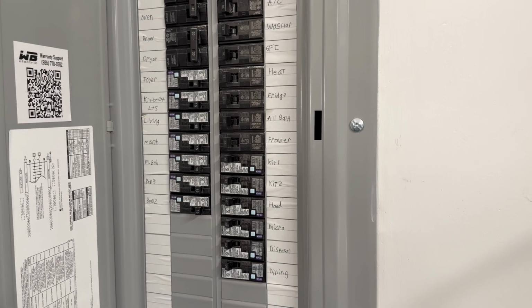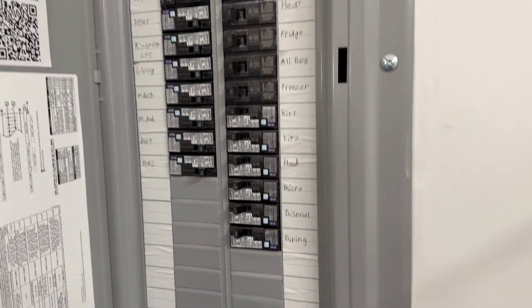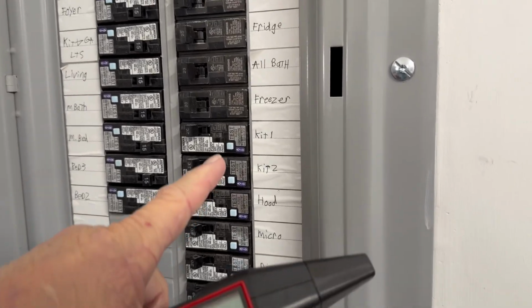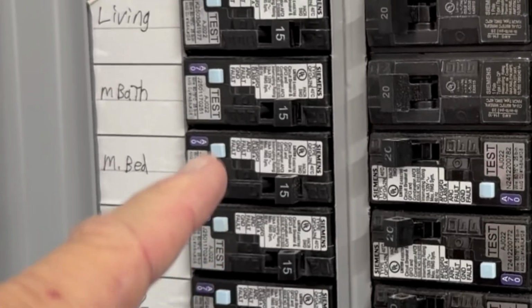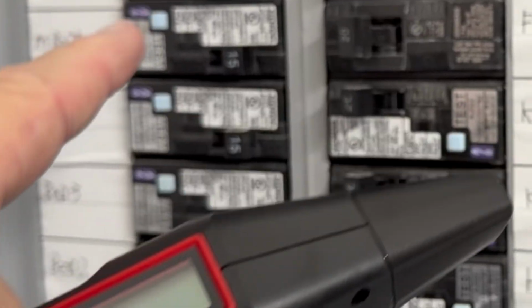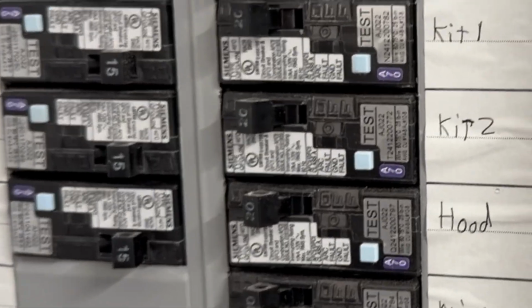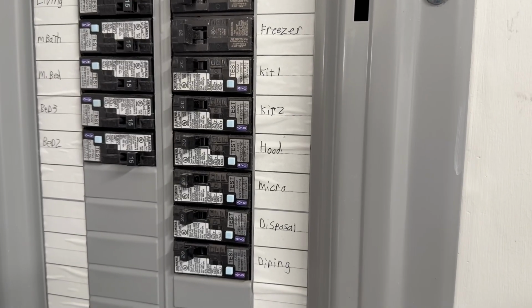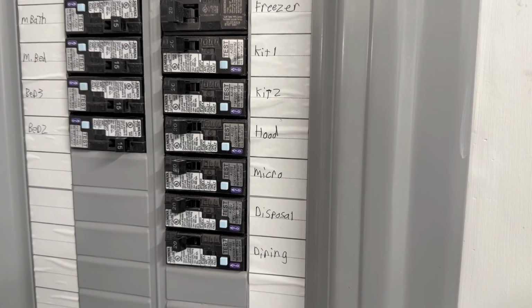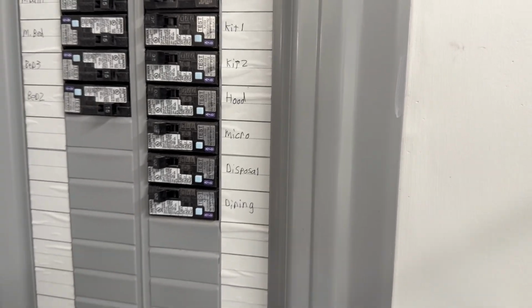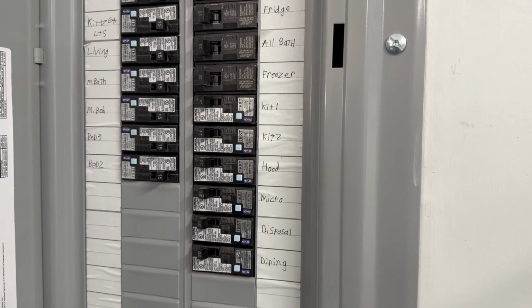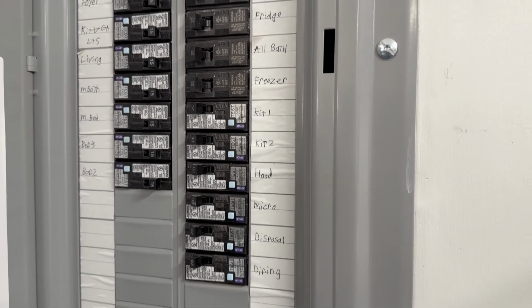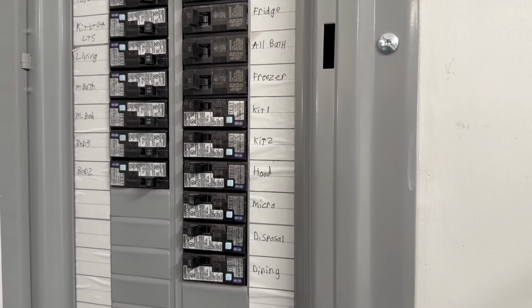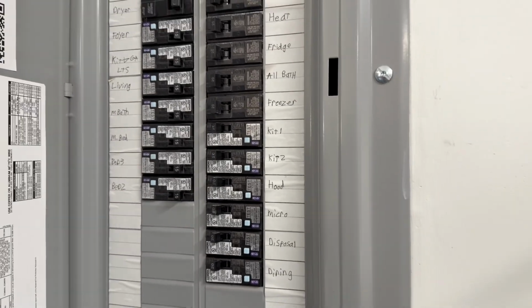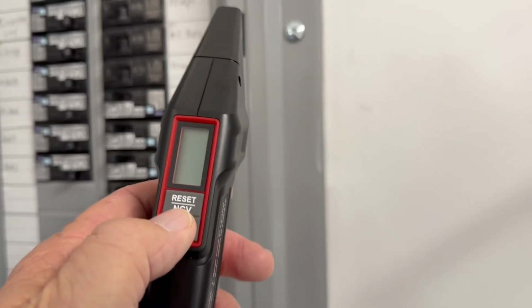Okay, we're at the electrical panel, and you might want to note there are several circuits here that have little white or light blue reset buttons. These are arc protector circuits that could trip. They're very sensitive to these testers, so you kind of have to ignore those. If that happens to be one of your circuits that you're trying to isolate, then you may have to do some other verification. So let's turn on the tester.